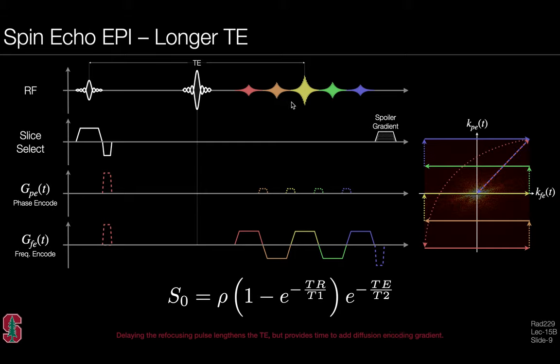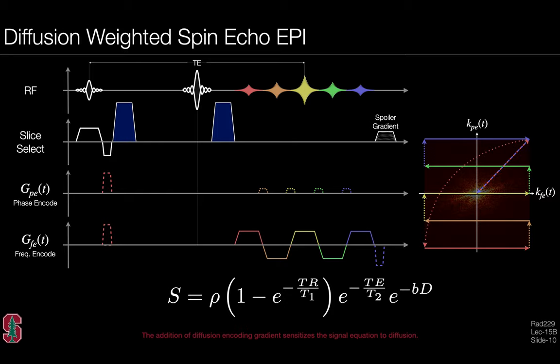The advantage of delaying the 180° pulse is that it opens time to insert two diffusion encoding gradients on either side of the refocusing pulse—both upright, since the spin system is flipped by the refocusing pulse, making the second lobe act as diffusion decoding. This gives us a diffusion-weighted spin echo EPI sequence. The spin echo signal equation is then modified to include T1 and T2 dependence plus an exponential term that depends on both the B-value and the underlying diffusion coefficient of the pixel, sensitizing the signal equation to diffusion.